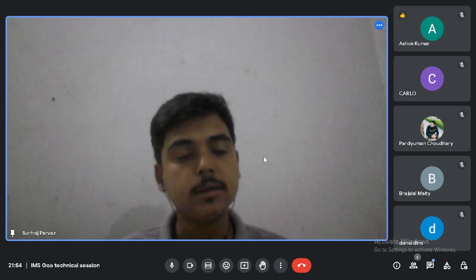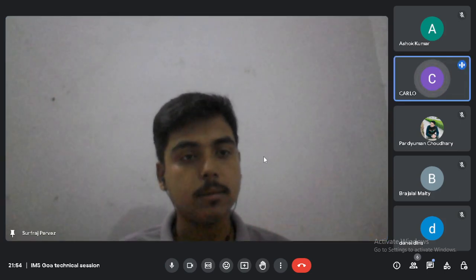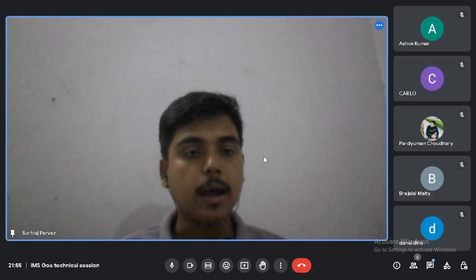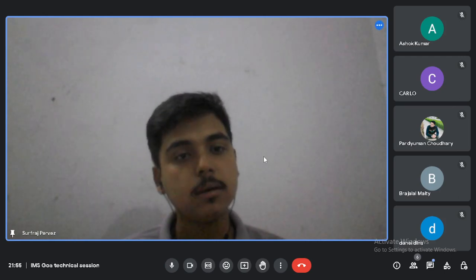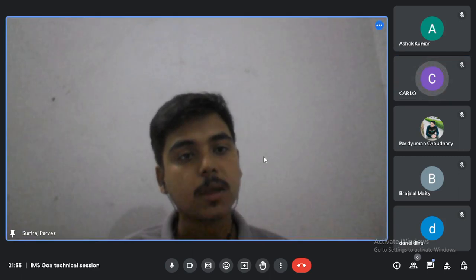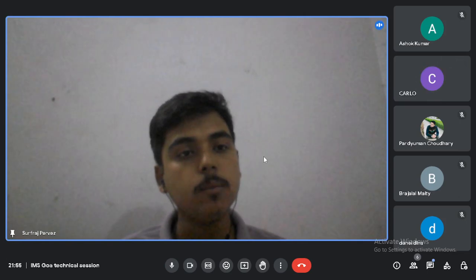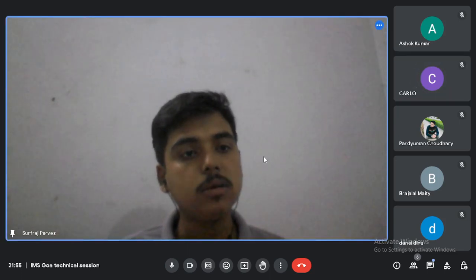Okay, so the other function is when we are feeding water into the boiler. So we know that water has air, and air has oxygen in it, and we need to remove it. Along with water and CO2, it can form carbonic acid. The chemical formula of carbonic acid is H2CO3, right? So this oxygen can react with water and CO2 and form H2CO3. Oxygen causes pitting corrosion.